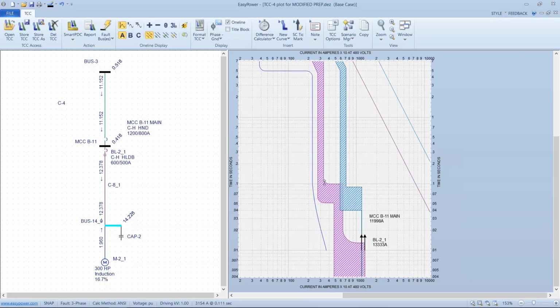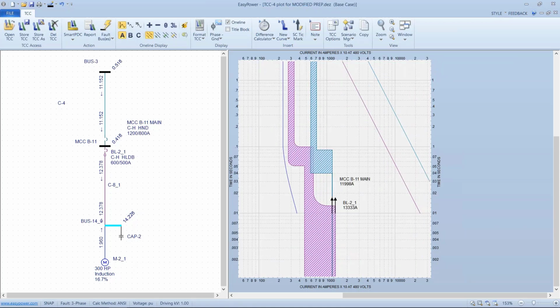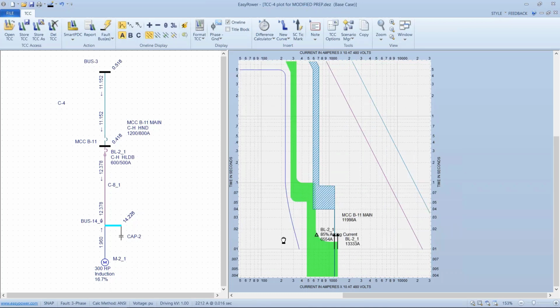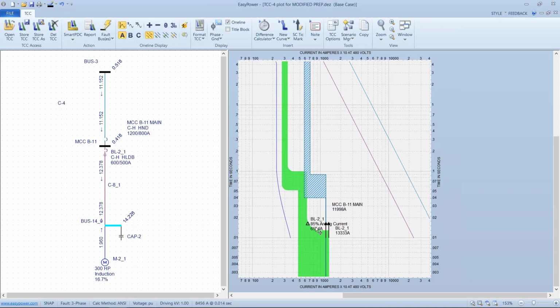And for some reason I was able to get closer on this particular starting curve than I did on the outboarded one. Now again, because this is faulted, these are symmetrical current values per phase for a single bus fault, and consequently they're being clipped at the maximum value that this breaker will see. These are symmetrical values and these are asymmetrical values. So BL21 we're showing here is going to see 12,378, whereas over here it's showing 13,333, and that's because it's asymmetrical current. If I right click and insert the arcing current, this will be the point that I can verify I have coordination between these devices at arcing current.